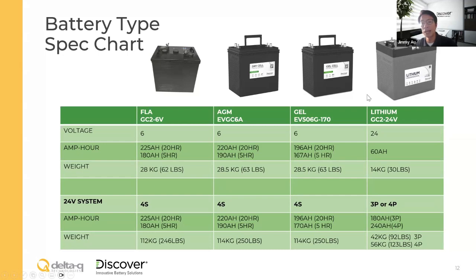So you would way surpass lead acid capacities. Weight as well, you can see there's a huge advantage, at least half the weight of lead acid. With a lead acid setup in 24-volt systems, you would be looking at close to 250 pounds or 115 kilos or so, versus with lithium, you're looking at a total of around 40 kilos or 92 pounds for 3 batteries in parallel, or 56 kilos or 125 pounds with 4 batteries in parallel.